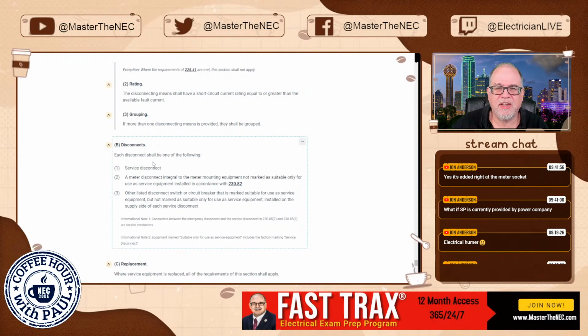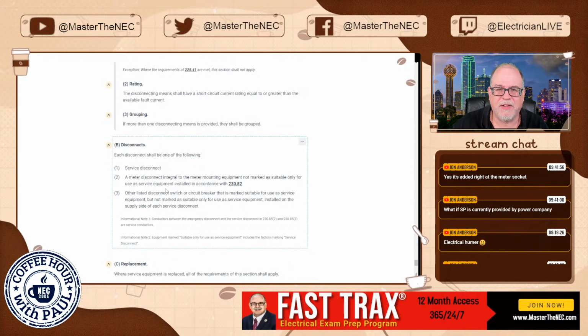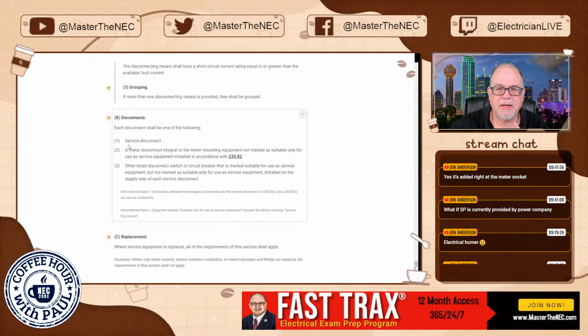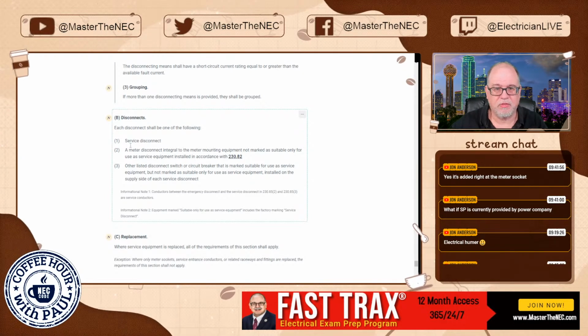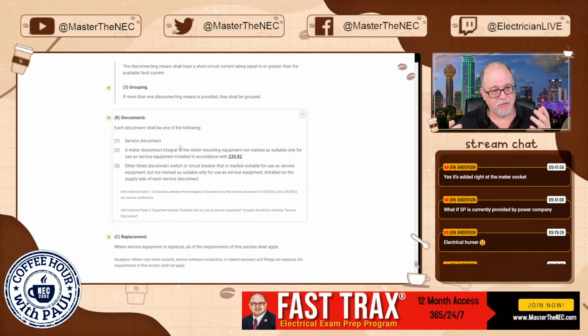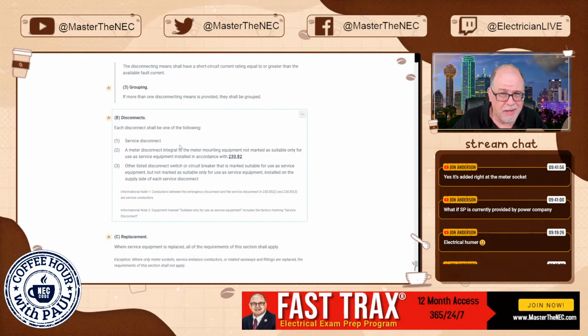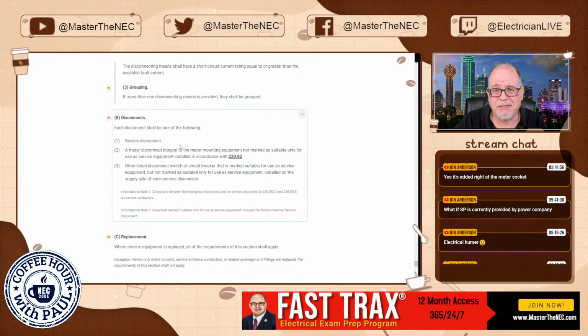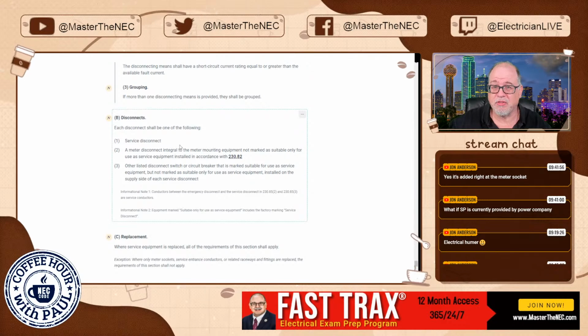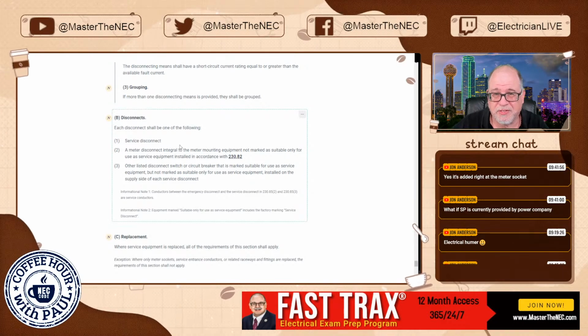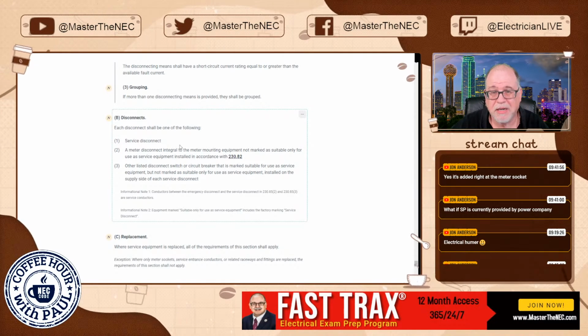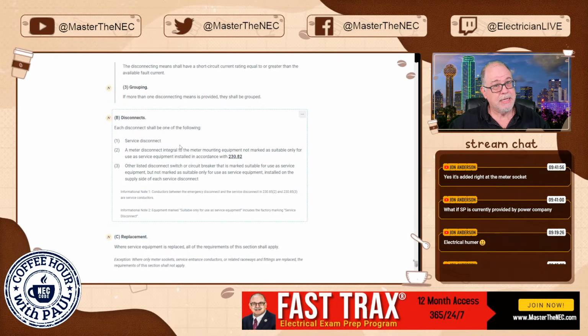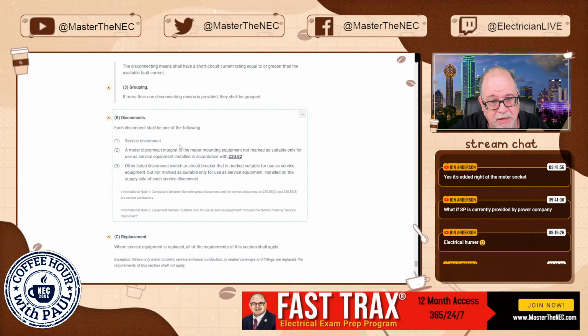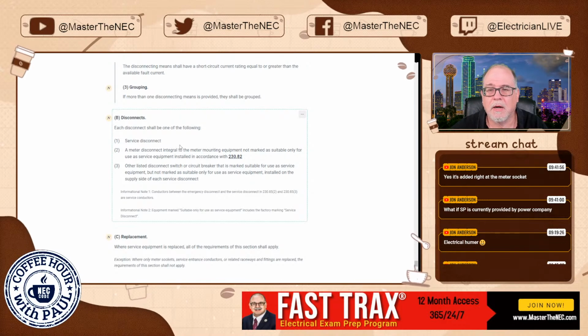Disconnects. Each disconnect shall be one of the following. Okay, it can be either one of these. It can be a service disconnect. So maybe you have a NEMA 3R panel out there, and it's got a main breaker out there, and maybe that breaker is not only your service disconnecting means, right, but it also would serve as your emergency disconnecting means, right? Makes sense? All right.